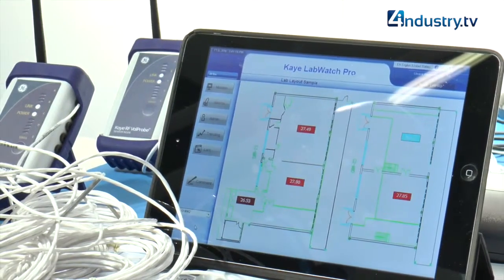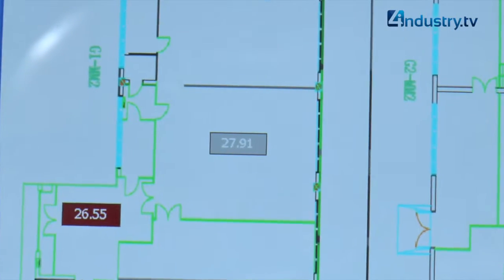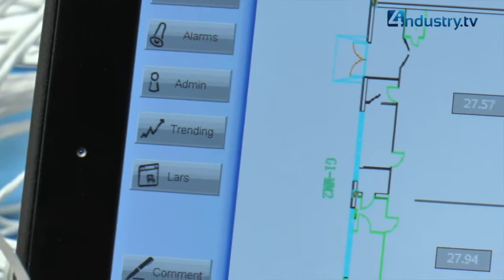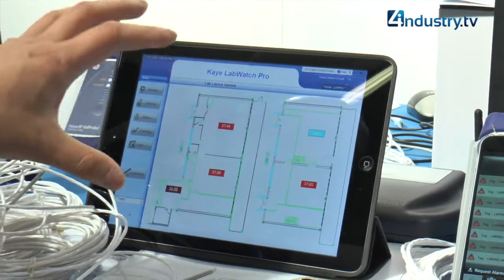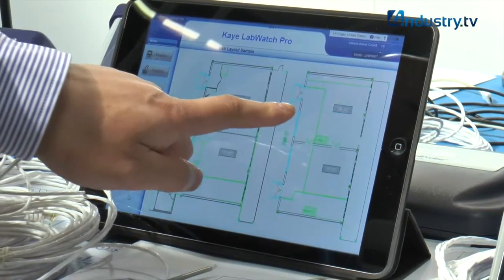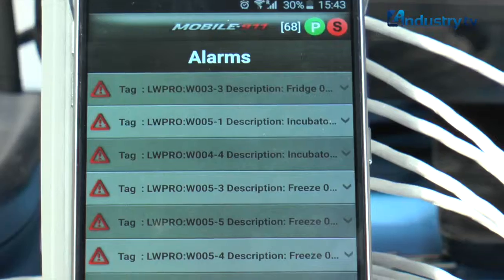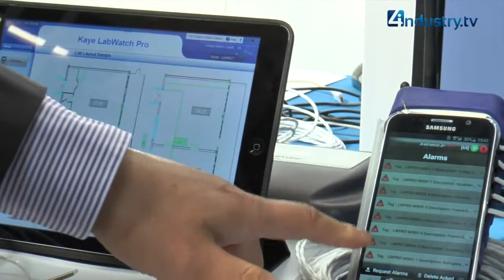Kaye LabWatch Pro is mainly used for the pharmaceutical industry to monitor environmental parameters. It has an interface and wireless sensors to measure temperature and other parameters. The signal is connected through a base station and goes into the computer system, displayed on screen. If temperature or other parameters go out of range, the system will alert the customer via email, telephone, and a smart app.